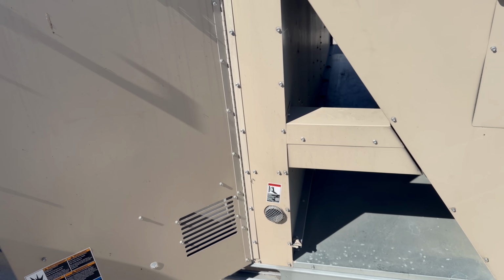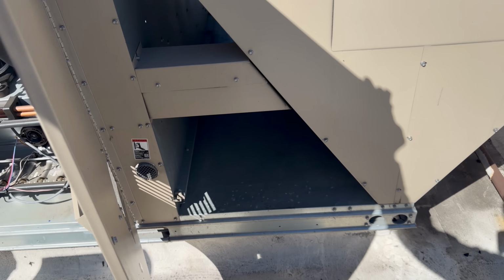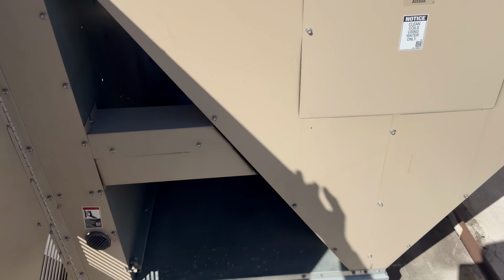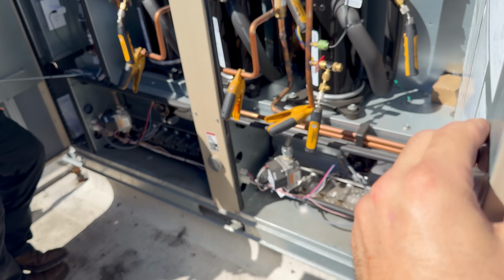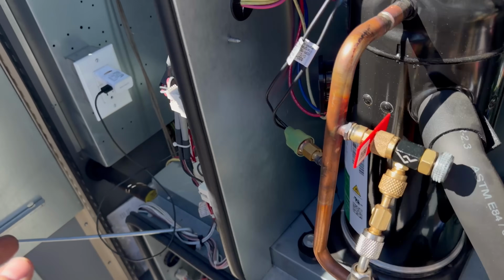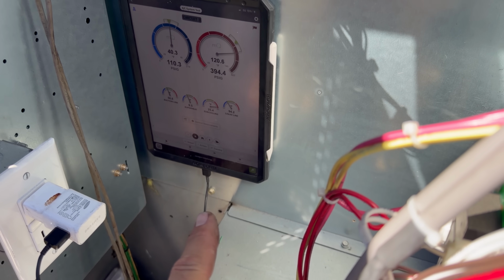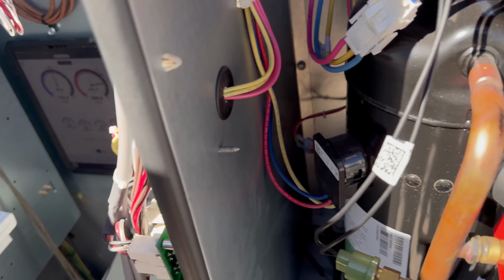So the third stage had an elevated head pressure because this door was sucked shut, only allowing air from the other side. Now that we closed it, our head pressure is slowly dropping. So it's gonna take some time, but that made a difference. And that's why I'm saying you gotta watch the airflow on these things.